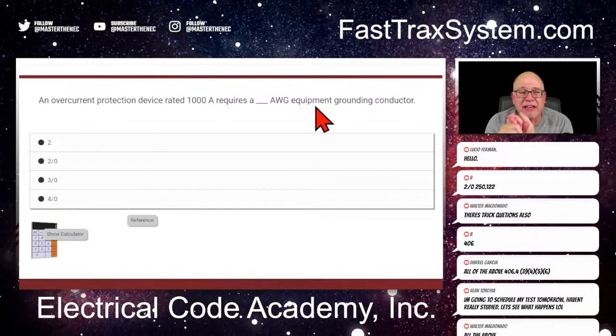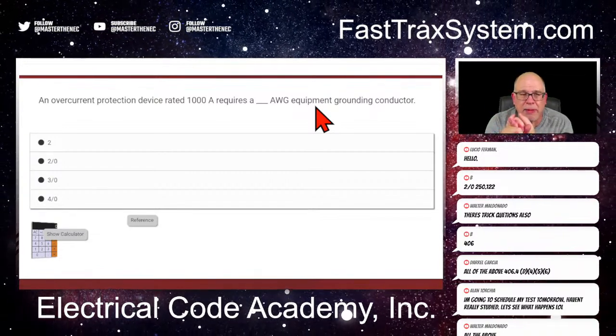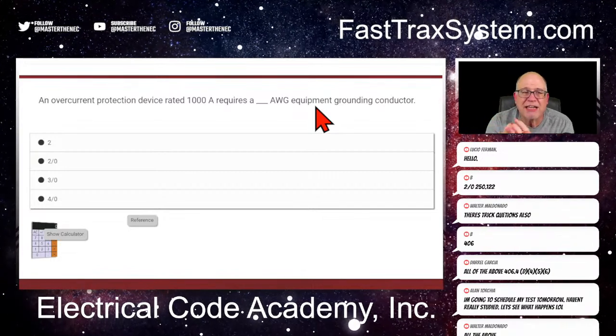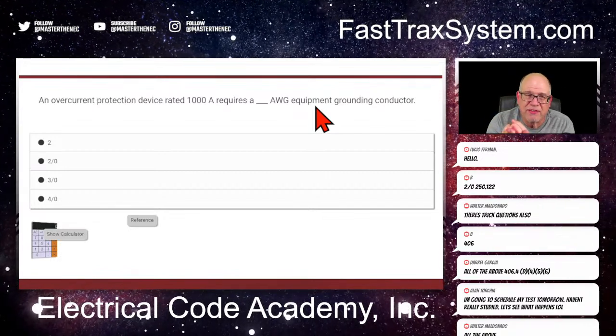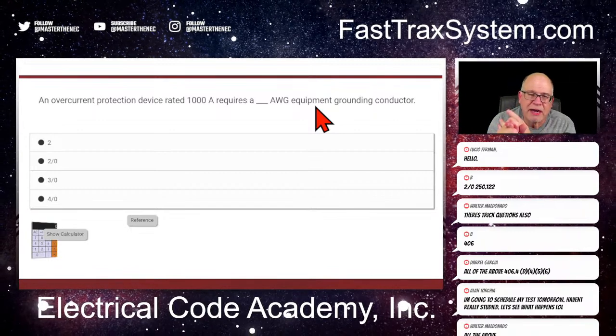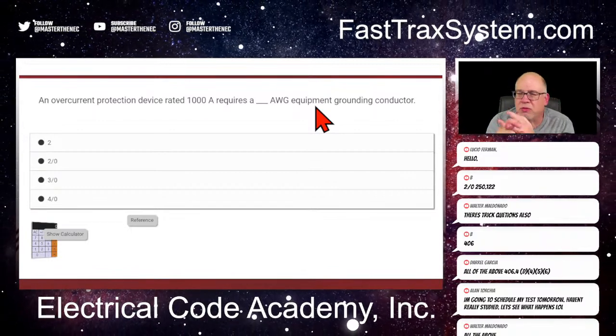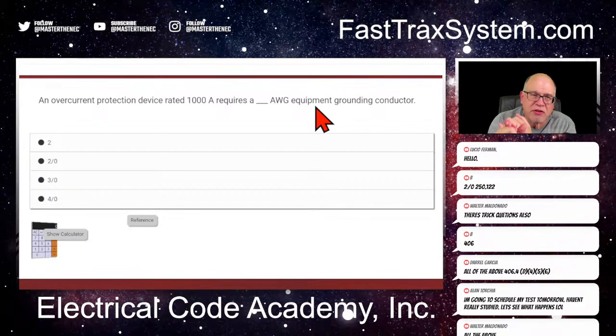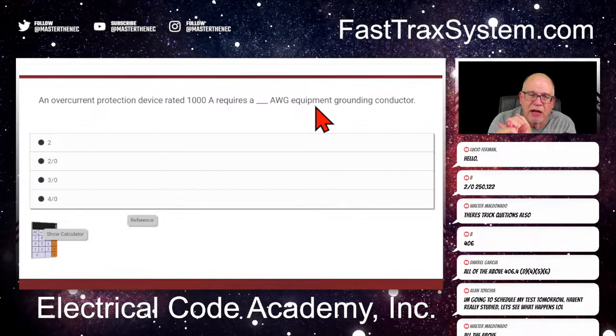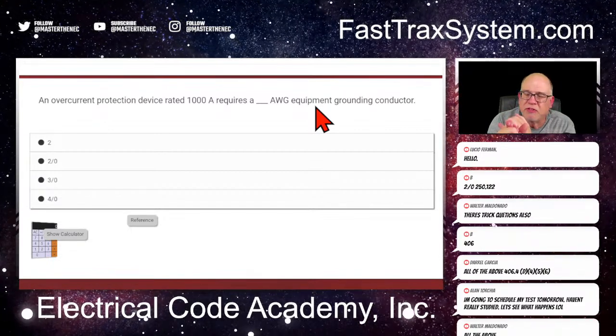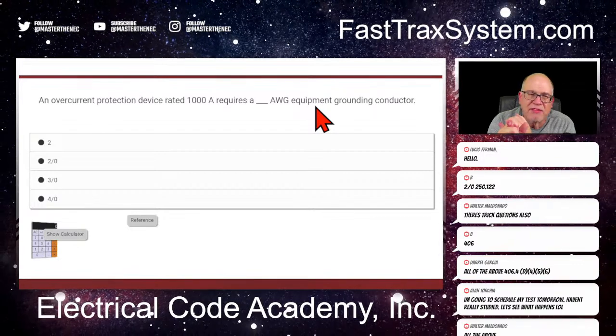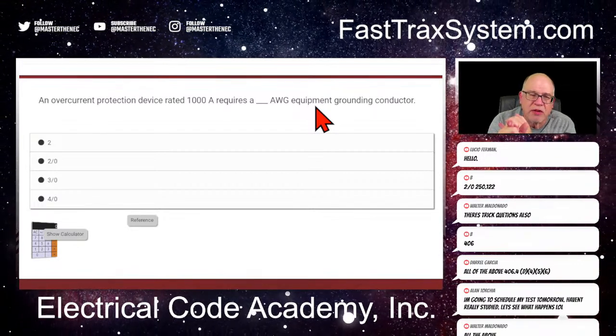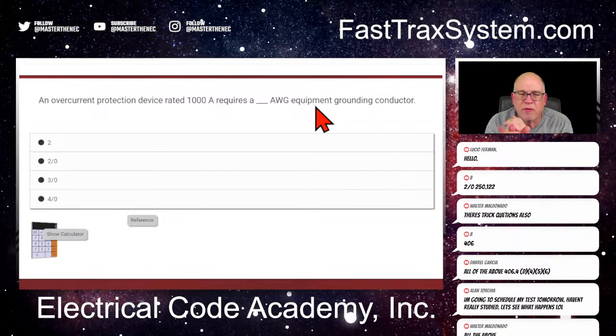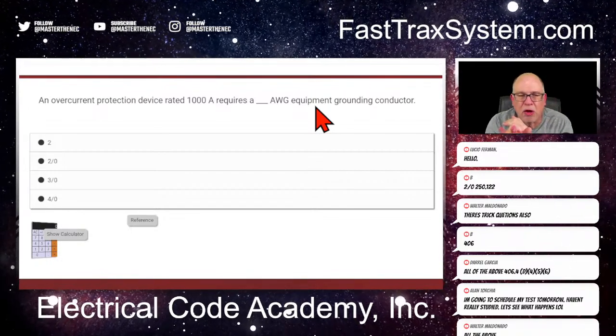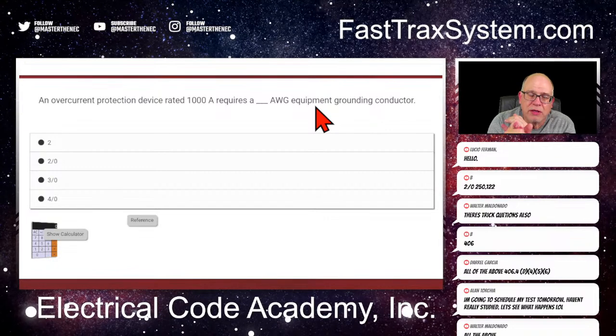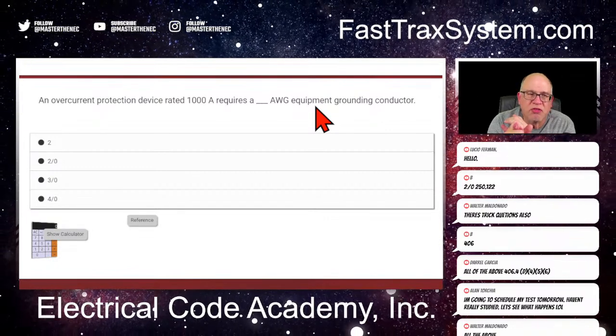So you should know to go to 250.122. Remember, some key things to remember in 250 tables: when sizing grounding electrode conductors, go to 250.66. When sizing equipment grounding conductors, go to 250.122. When sizing supply side bonding jumpers, minimum size for the grounded conductors for the service, the supply side bonding jumpers, all main bonding jumper minimum sizing, even though 250.28 and 24 and all that will ultimately send you to 250.102C.